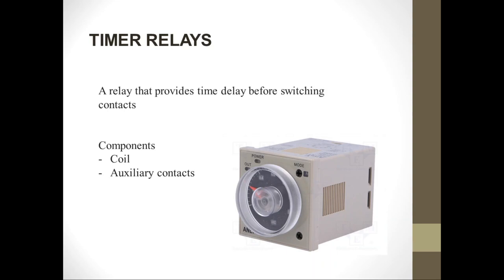Before it switches its auxiliary contacts, the timer provides a time delay, as the name suggests. Depending on the type, the delay process may vary. There are two types of timer relays: the on-delay type and the off-delay type. For the on-delay type, when the coil is energized, the timer provides a time delay, and after the preset time, the auxiliary contacts switch position.